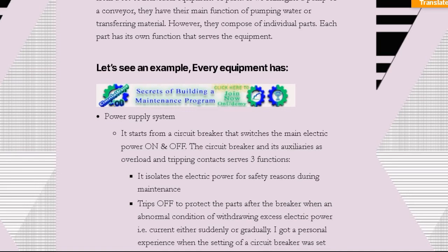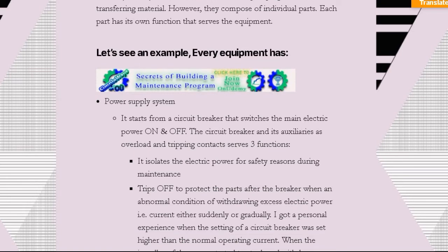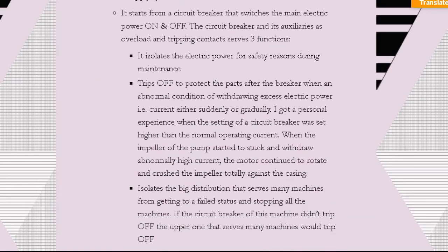One function is to switch on and off, to isolate the electrical power for safety, because we are doing maintenance, for example. Another function is to trip, to protect the part. So if some motor is overloaded or some part of the circuit is overloaded, it consumes more current than its design, it protects its load, it protects the motor from the overload, or protects from the spike in the current.